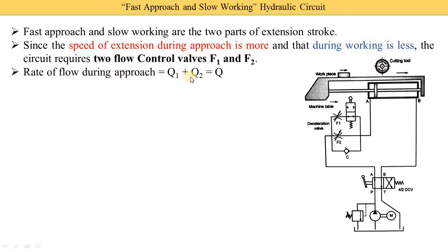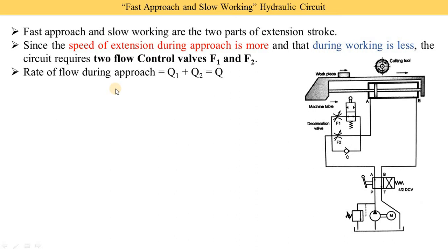Rate of flow during approach is Q1 plus Q2, which equals Q total. Between the directional control valve and the hydraulic cylinder, flow control valves F1 and F2, and check valve C are installed. F1 is switched on or off by a 2/2 directional control valve. During approach, both F1 and F2 are open, so oil is supplied with quantity Q1 from F1 and Q2 from F2, and their sum Q1 plus Q2 equals Q.